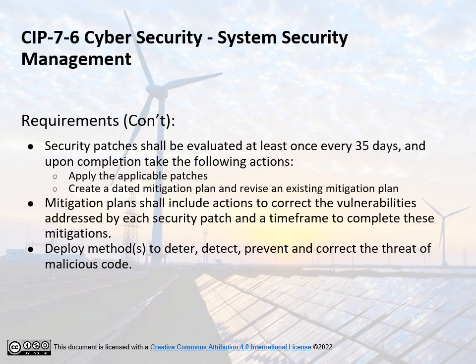Mitigation plans shall include actions to correct the vulnerabilities addressed by each security patch and a time frame to complete these mitigations. For each plan created or revised, implement the plan within the time frame specified, unless a revision to the plan or an extension to the time frame is approved by the CIP Senior Manager or delegate. Deploy methods to deter, detect, prevent, and correct the threat of malicious code.